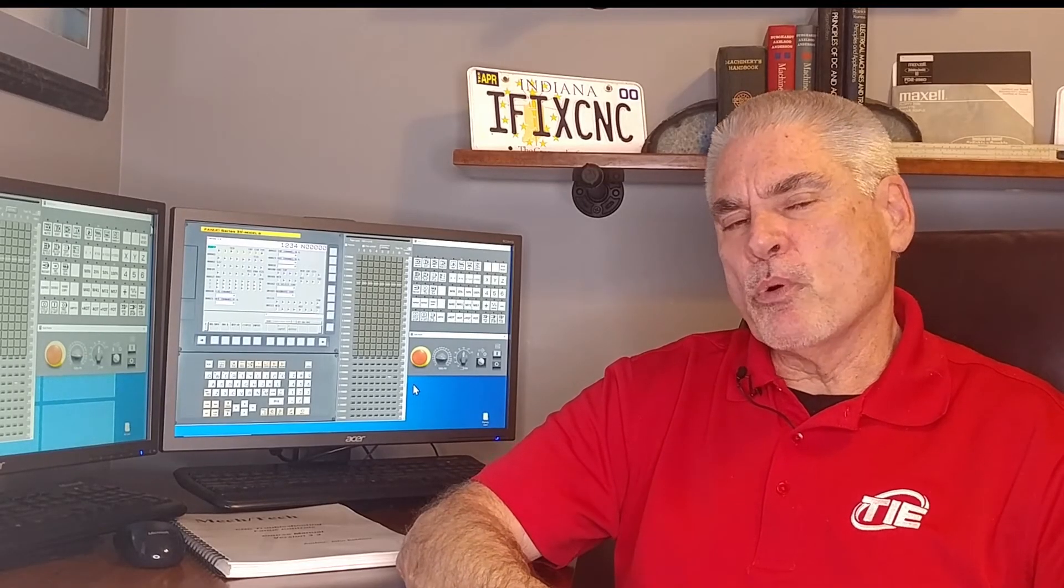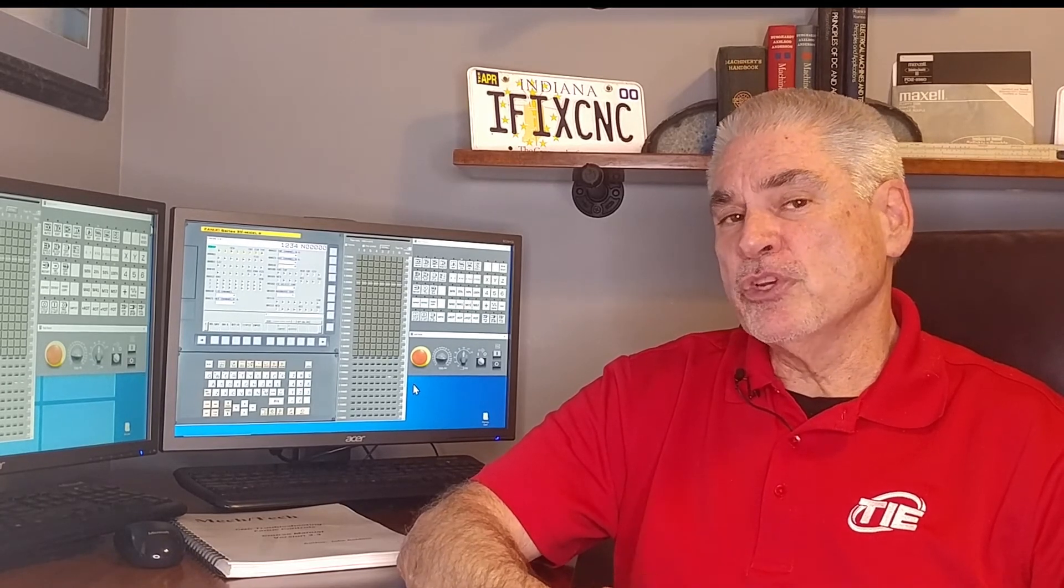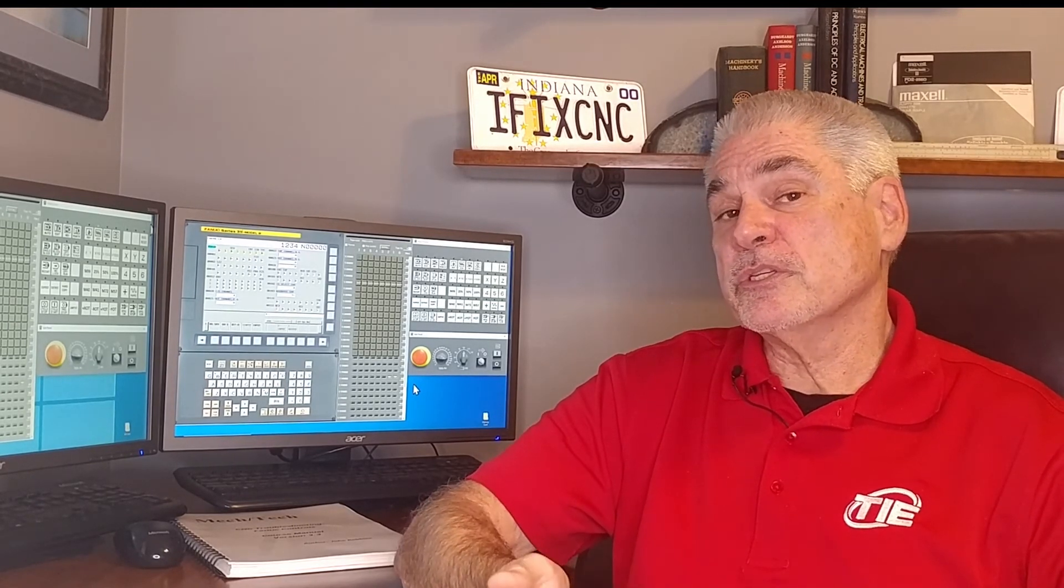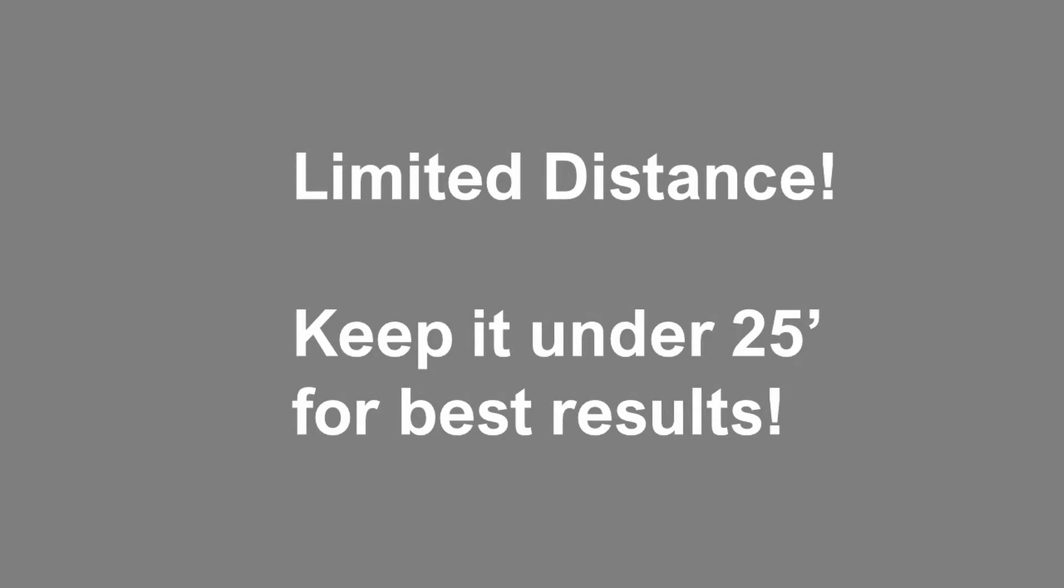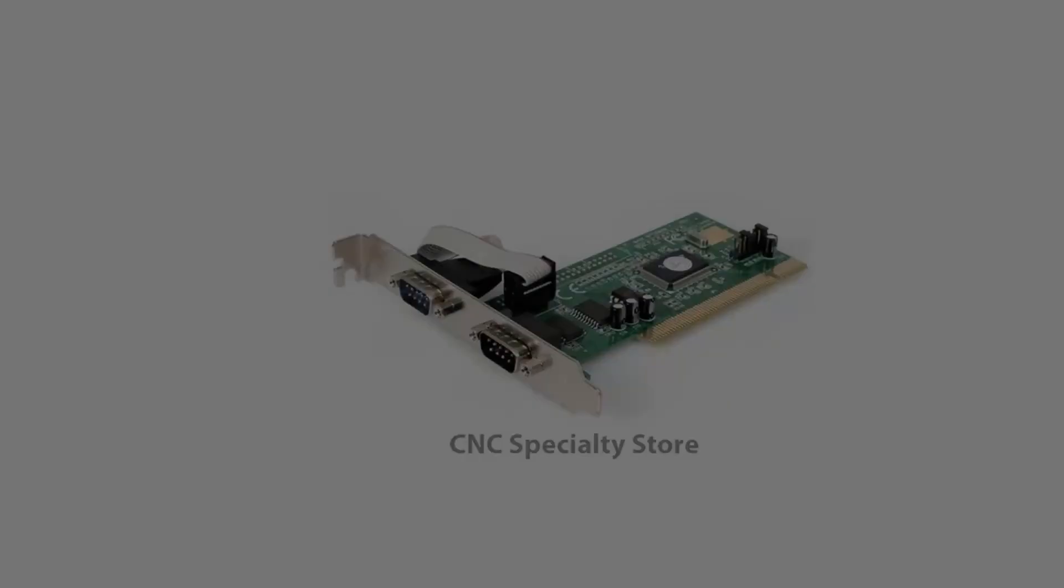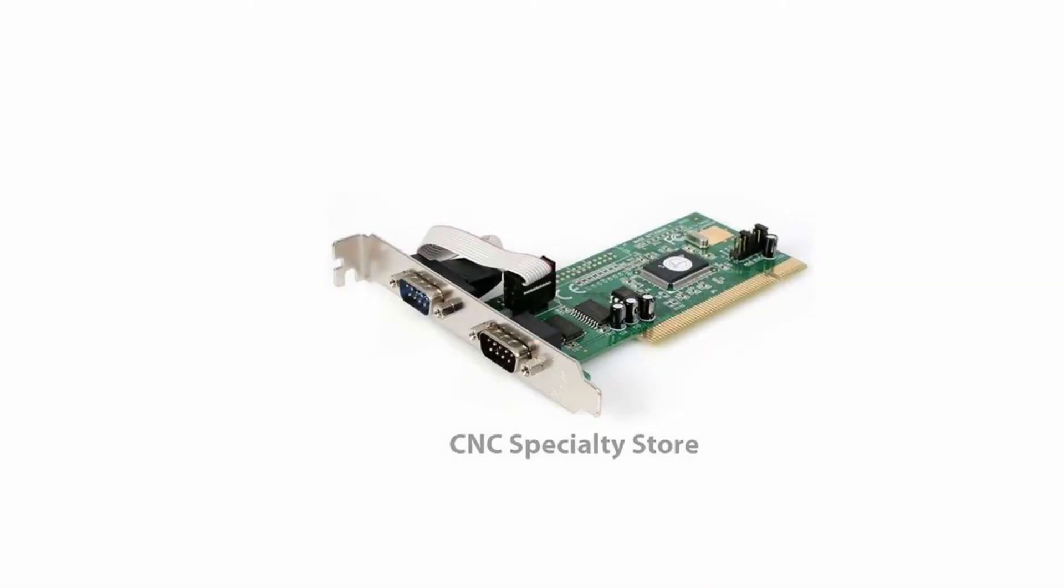The USB ports have a very low voltage and current capability. In order to convert the USB signal into an RS232 signal, you need to step the voltage up. That reduces the current capability even more. Because of this, the distance that the signal can be sent is very limited. I recommend that you keep your cables to less than 25 feet. Otherwise, you may experience signal degradation. If you need to transmit over a long distance, purchase a true RS232 port and install it in your PC.